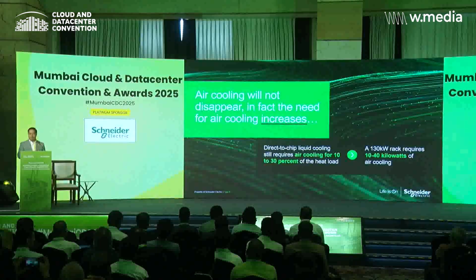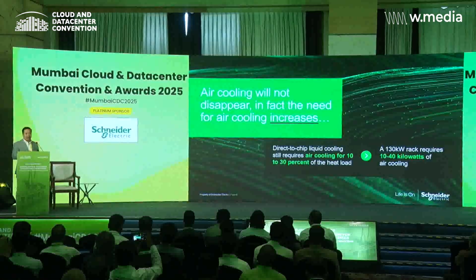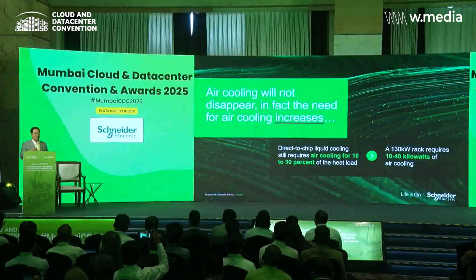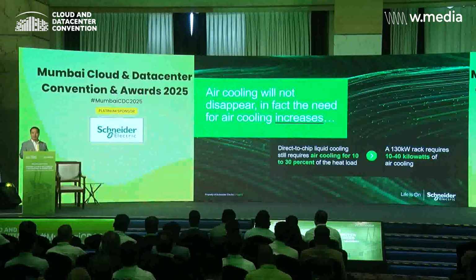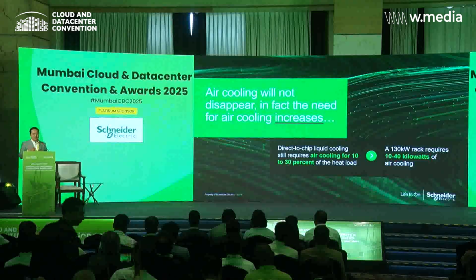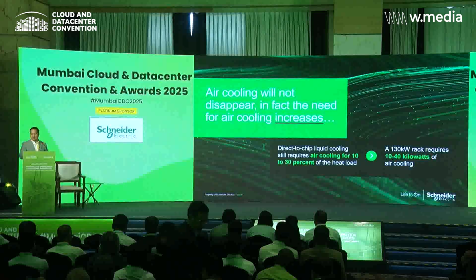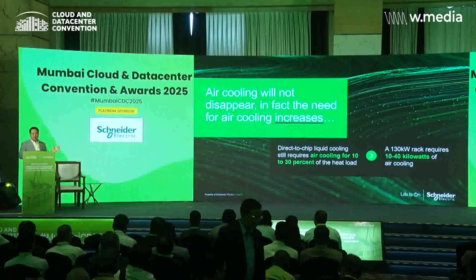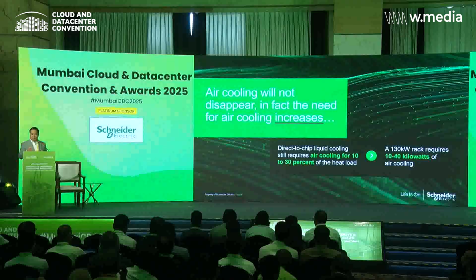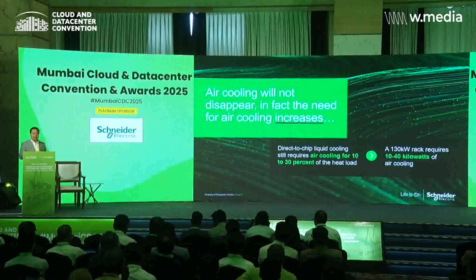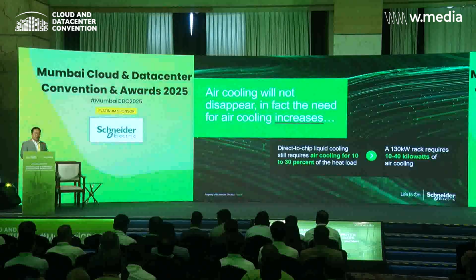But as we talk about liquid cooling, we cannot forget about the air side. Air side is still crucial to remove the rest of the heat. Even today, at 130 kW a rack, between 10 to 40 kW—roughly 20% of the heat—still needs to be managed by air.